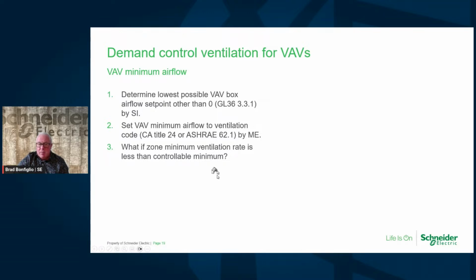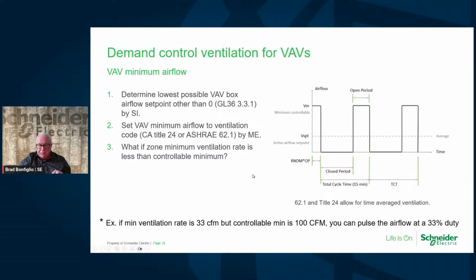And then what if the zone's minimum rate is less than controllable? So this happens quite a bit, where the actual set point that we want can't be controlled to there. And I'll show you an example. In this example at the bottom, if you have a ventilation rate of 33 CFM, but I can't control it lower than 100, then to get down to that 33%, they actually duty cycle it. Okay, they'll go on and off. So it'll actually go to 0 and then it'll go back up. Over time, you'll hit the average of the 33 without actually being able to control from there. So this is a different way that we've done this before on VAV boxes.